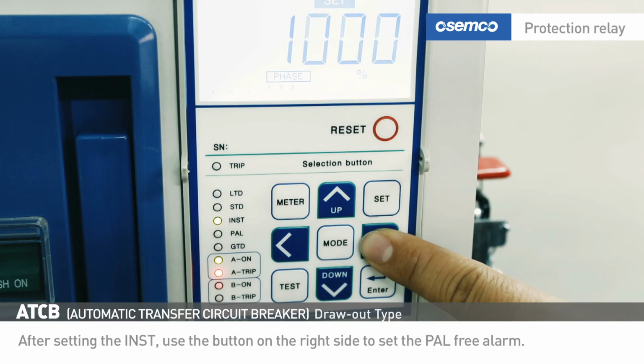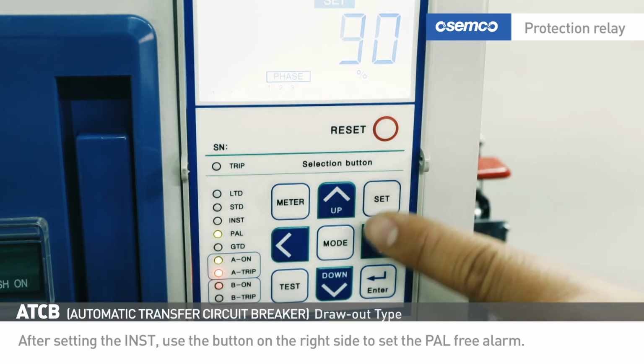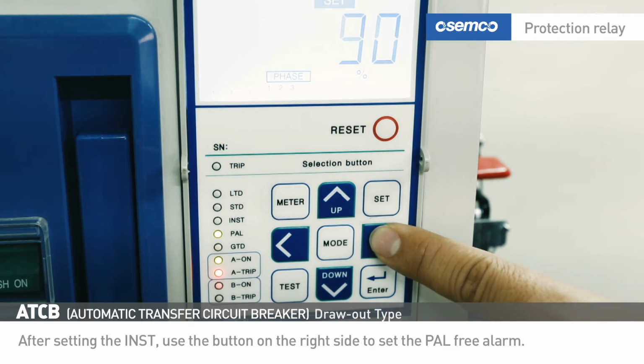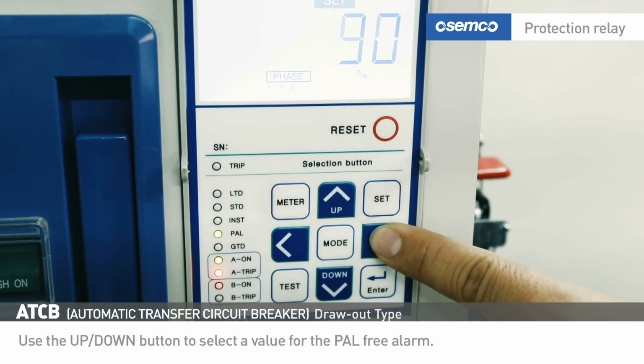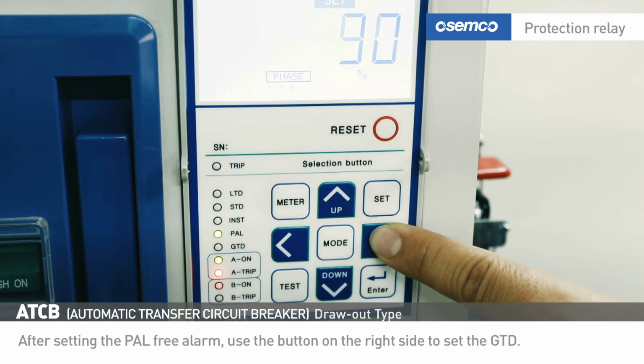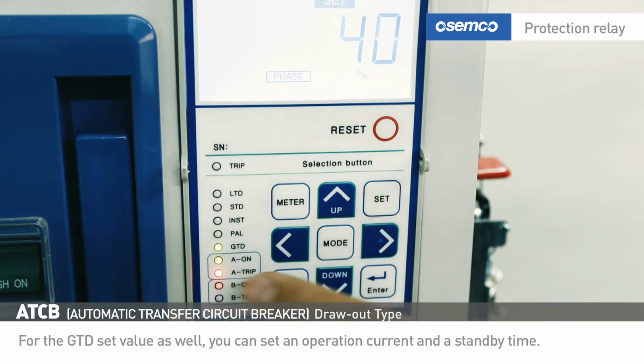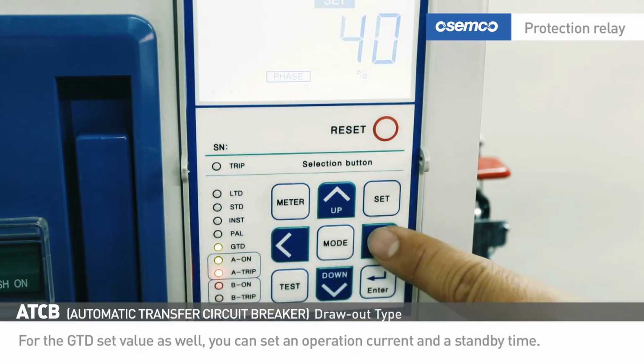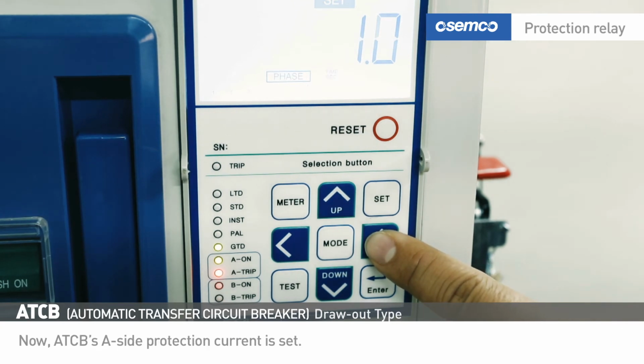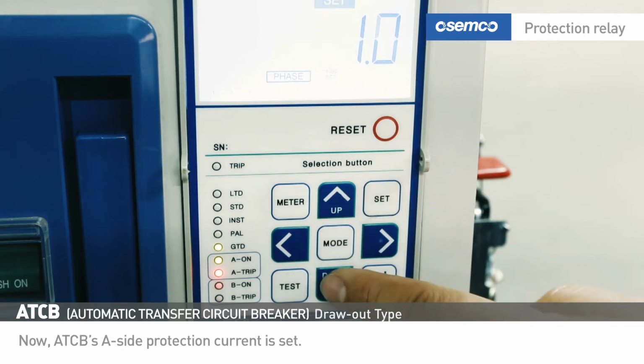After setting the INST, use the button on the right side to set the PAL free alarm. Use the up-down button to select a value for the PAL free alarm. After setting the PAL free alarm, use the button on the right side to set the GTD. For the GTD set value as well, you can set an operation current and a standby time. Now, ATCB's A-side protection current is set.